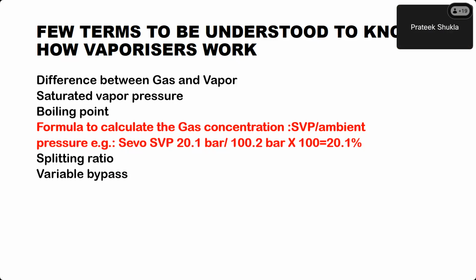So all the fresh gas flow which is coming from the flow meter, all of them do not enter the vaporizing chamber to carry the vapor from the volatile anesthetic liquid that is filled in the vaporizer. Part of it will go, depending upon the concentration that we keep in the dial, and the rest will go straight without entering the vaporizing chamber. The part that goes into the chamber is called the carrier gas, and this carrier gas mixes with the rest of the fresh gas flow which is not carrying any vapor, and the ultimate output will be decided by the percentage of gas that is going into the vaporizing chamber and the part that is not going into the vapor. So that is called the splitting ratio. This terminology is also very important.